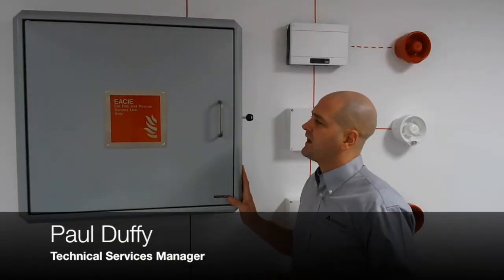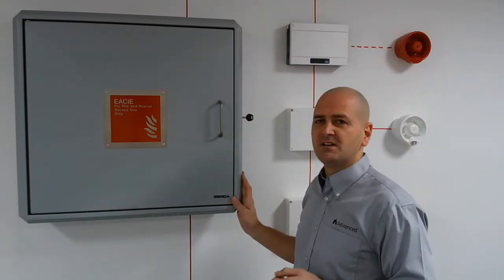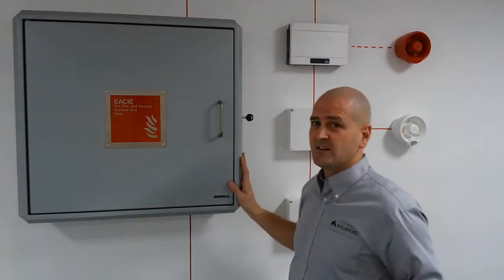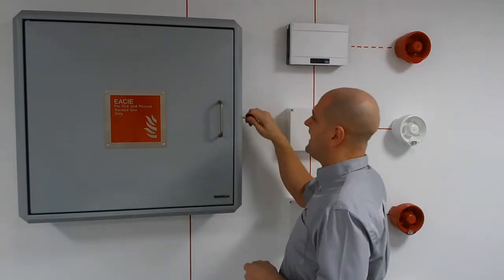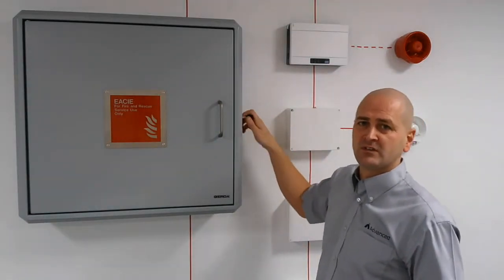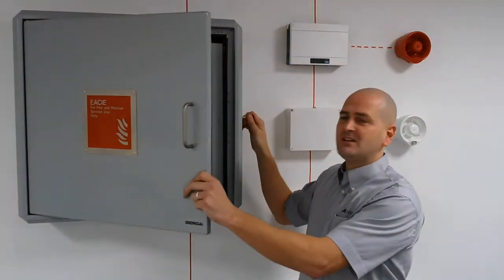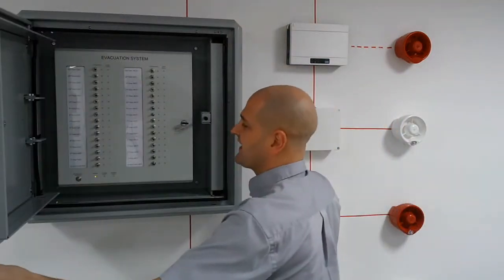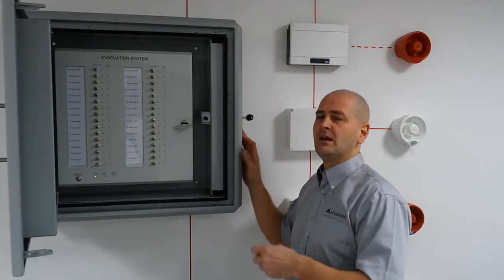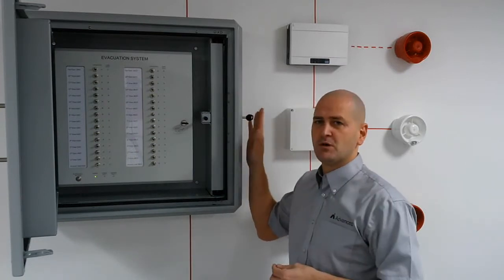So we identify some components. This is our security rated enclosure, the STS-205. You can think of it as a basic safe mounted onto the wall, and it has a designated key which is held by the fire and rescue services. The building owner or the responsible owner should also have one of these keys in place. This key will obviously need to be requested whenever you service and maintain the system, or want to install, test, or program the system. We need to make sure we get access to the key.